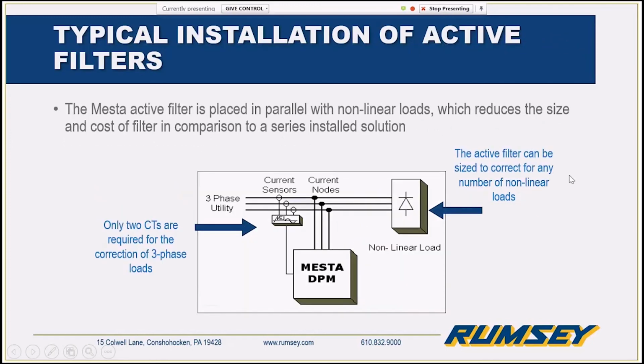And we'll look at a more detailed example of an installation diagram a little later on, but here's a look at how the active filter would be set up. So the active filter is installed in parallel, and there's a couple of unique advantages to that parallel installation. First, being in parallel, we only need to be sized for the corrective current required. So a good rule of thumb is harmonics are about a third. So if you have 900 horsepower worth of VFD load, you might be able to correct it with one 300 amp filter. Doesn't matter the number of drives to total that 900 horsepower of VFD load, but that's a nice cost savings that an active filter can bring you.